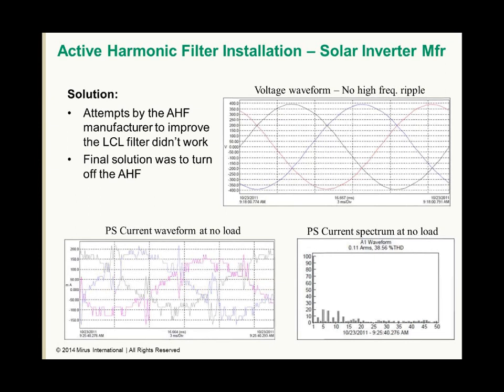So we informed the active filter manufacturer of this problem, and their attempts to improve the LCL filter, which is the filter that addresses these high-frequency harmonics due to the switching of the IGBTs, didn't work. They tried several attempts and improved it a little bit, but it just allowed the power supply to last maybe a couple of minutes longer. It would still fail as soon as it was powered up. The only final solution was to turn off the active filter. So they ended up having no form of treatment on the rectifier and in their inverter test lab.